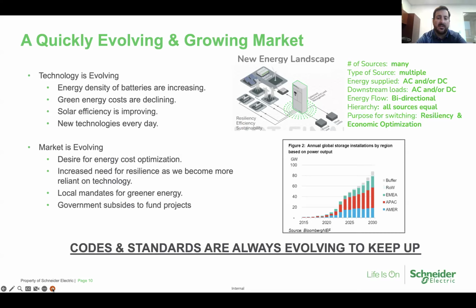It used to be very hierarchical, where power flowed from the top down, meaning the utility through your distribution down to your loads. But now we're seeing the power flow in both directions, because if you think about that hierarchy of a distribution network, we're seeing things that can act as sources down by where the loads traditionally were. Things like solar are coming in from the bottom of your distribution system, and battery energy storage. So things that were traditionally thought of as loads can actually be sources now as well. But beyond that, some of those, like battery energy storage, can actually be both. If it's charging, it's a load. If it's discharging, it's a source.